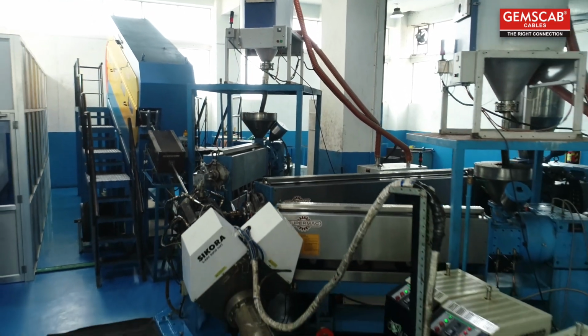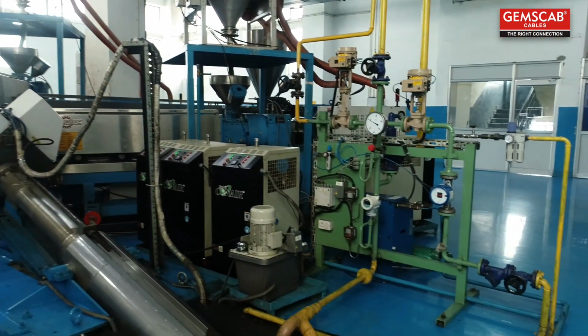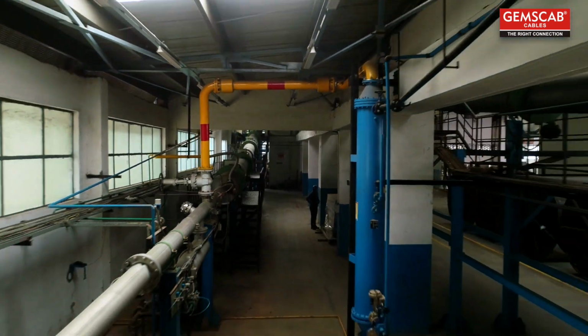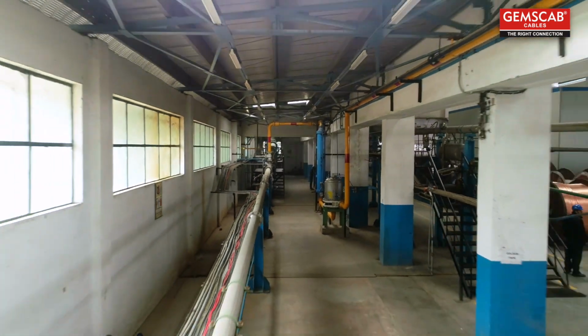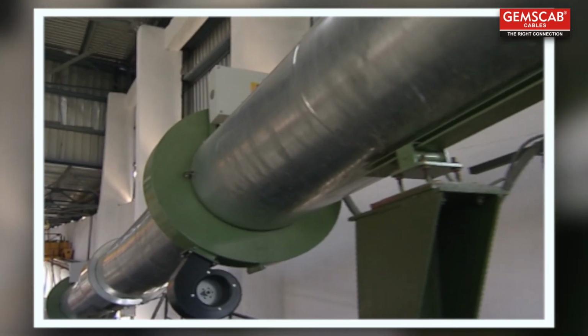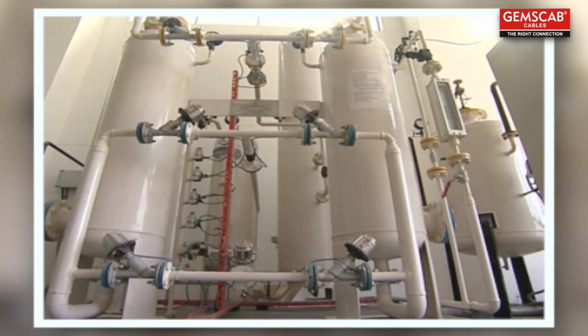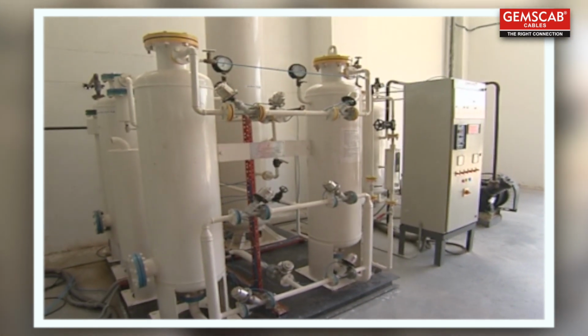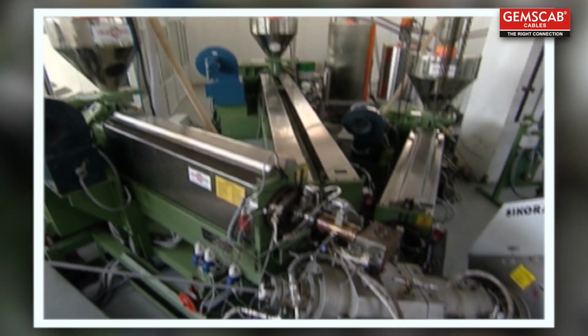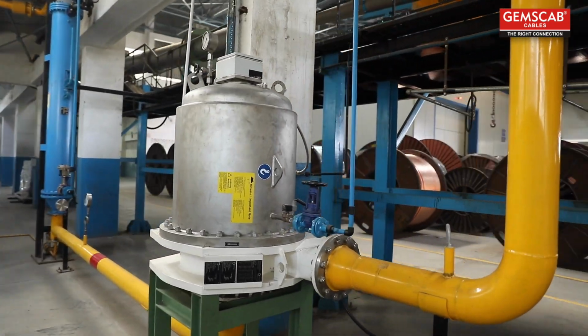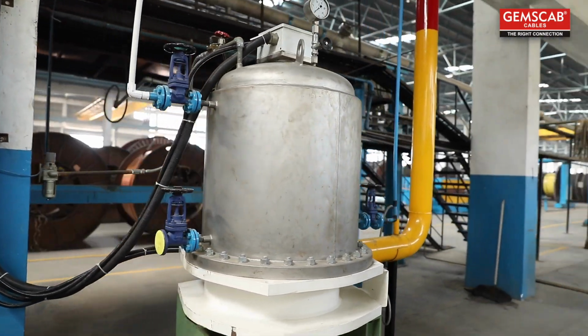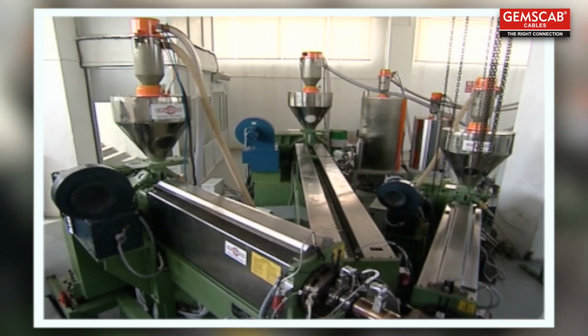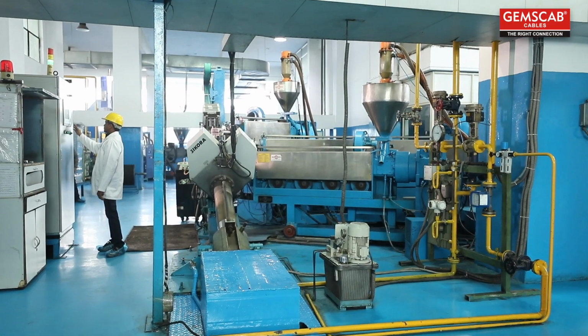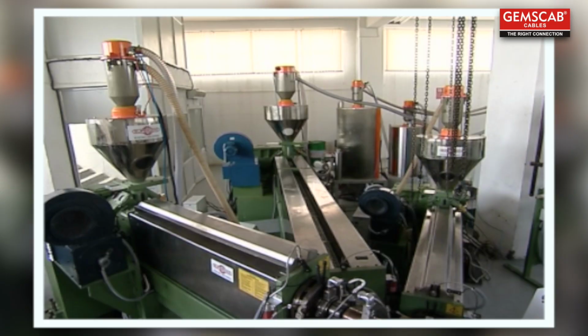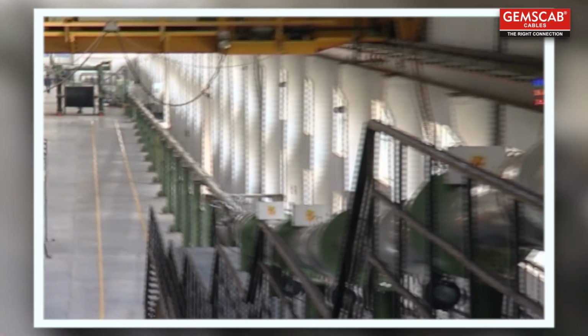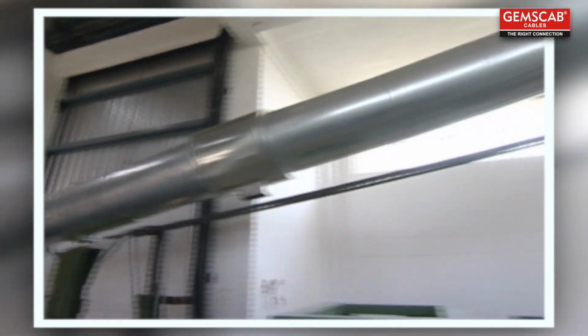Thereafter, the extruded core enters the vulcanizing line known as CCV line, continuous catenary vulcanizing, and the XLPE insulated core is cured in the process. In CCV line, inert atmosphere is maintained by the nitrogen gas, which is at high pressure and high temperature. This process is popularly known as single-point triple extrusion CDCC, completely dry cured and cooled curing process. Triple extrusion and CDCC process ensure contamination-free cores. All 3 layers are bonded and core has least eccentricity and ovality. Insulation itself is free of micro voids and with no moisture content.